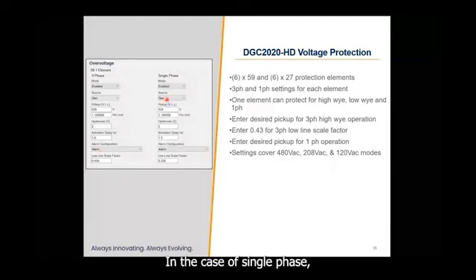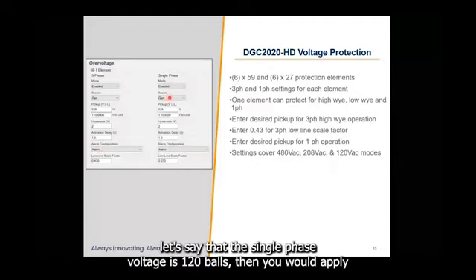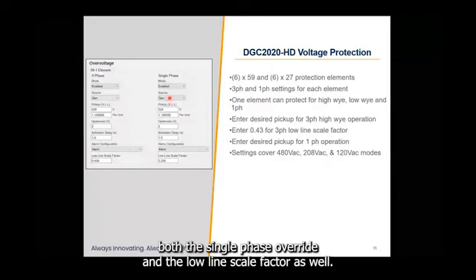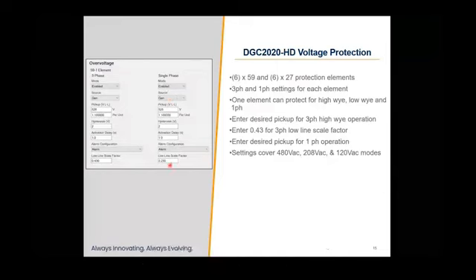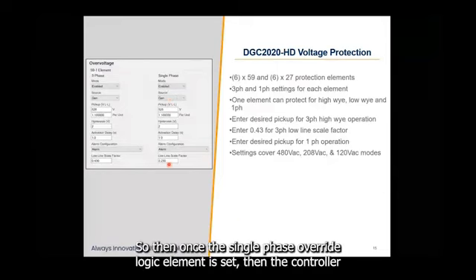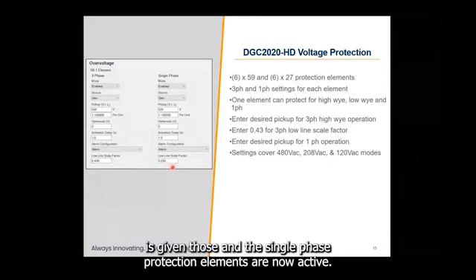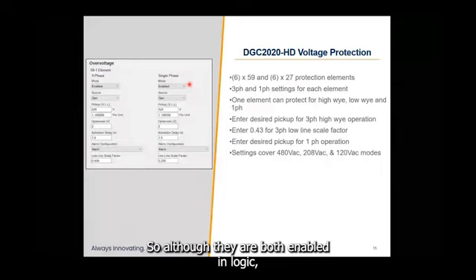In the case of single phase, let's say that the single phase voltage is 120 volts. Then you would apply both the single phase override and the low line scale factor as well. So then once the single phase override logic element is set, then the controller is given this, and the single phase protection elements are now active. So although they're both enabled in logic, only one is active at any given point in time.